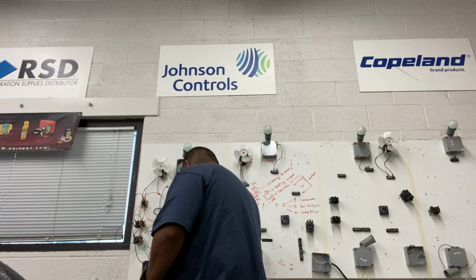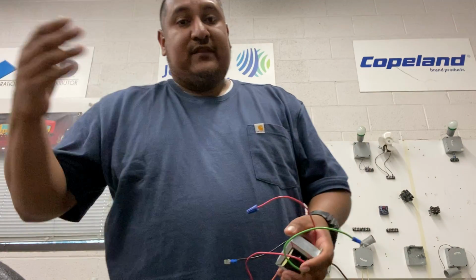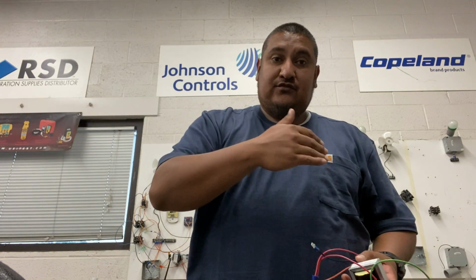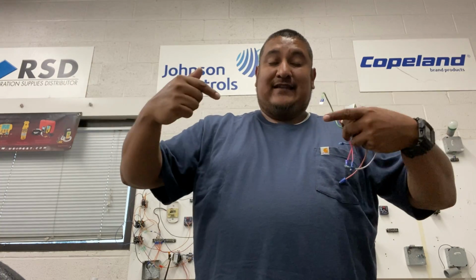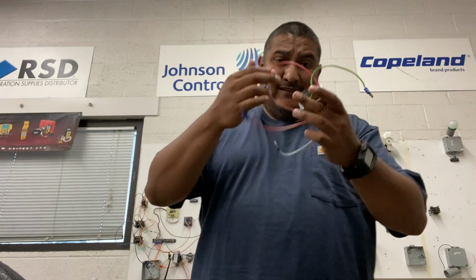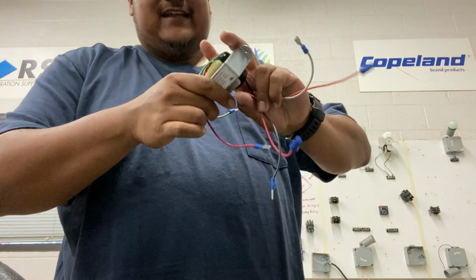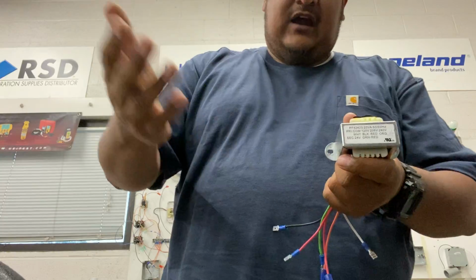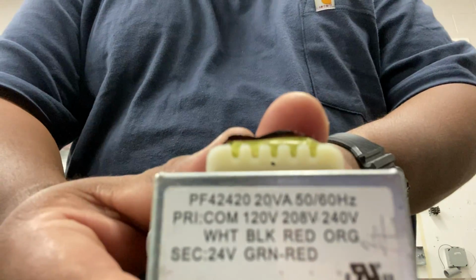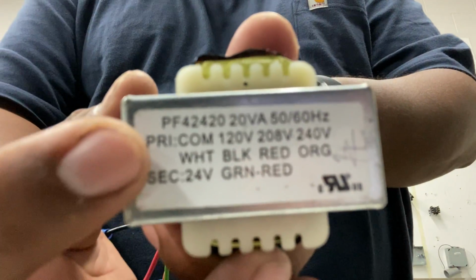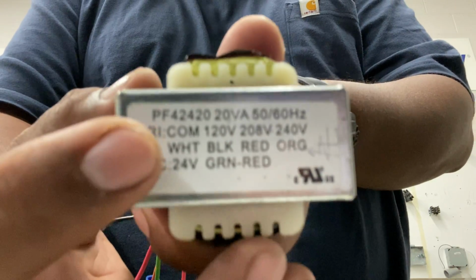Now, we talked about a transformer, right? So a transformer is going to be hooked up directly to that guy on the line side, on the incoming side, right? You guys got to remember that anything that's coming in to that contactor, you can tie into that guy, and you will always have power coming out of it, because that guy will not shut down. It will stay constant as long as that disconnect is active, right? So this guy here is going to get set up to the line side of that contactor, so we can always have power, right?